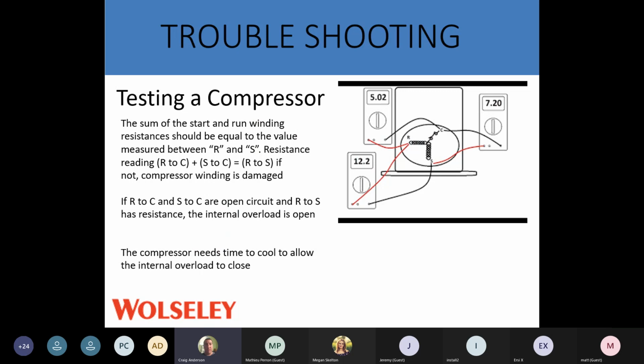Testing a compressor. You've got power to the compressor, everything else is running, the fan motor's running. So we want to check the windings. We want to do a resistance check reading on the compressor to see if the winding is damaged. So, easy little test. I suggest testing it on the compressor. You can test the wires first before you take everything apart and get to the compressor, but it's always a good idea to test it right on the compressor. So if you go from your R to your C, and then from your S to your C, and you add those together, they should equal your R to your S. If it doesn't equal, then we have something going on internal with the winding.